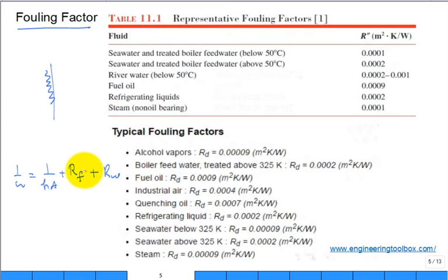You're adding a resistance to fouling plus then the resistance due to the wall, etc. So how do they modify it? Well, for a bunch of different fluids and different service conditions, and these change over a number of, while it's in service, sometimes they monitor the resistance. They can detect how the heat exchangers are performing, and then they'll take it out of service and clean it. Physically go in there and remove the scale and remove the deposits to reduce the fouling factor, get it back to zero. All right. Well, you can see this is how the textbook reports a fouling factor. What is that? Is that R double prime?